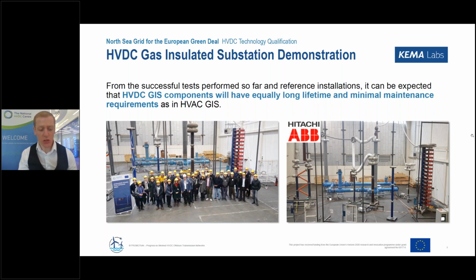Every block included switching tests and lightning pulse tests, but each block had a different DC voltage by reversing the polarity or being with or without current, so up to 4,000 amps for some of the blocks. The outcome of this long-term testing was that the DC GIS has a similar lifetime to that of its AC equivalent.